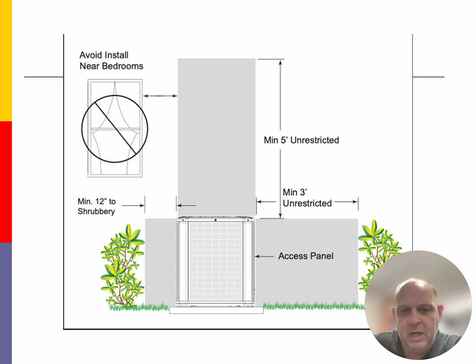As far as the access panel, getting into the electrical box, we want 3 feet in front of that unit so that we can get in there and easily work. And then above a unit, and this is depicting a Rheem type of unit, we want a 5 foot unrestricted area above that unit.